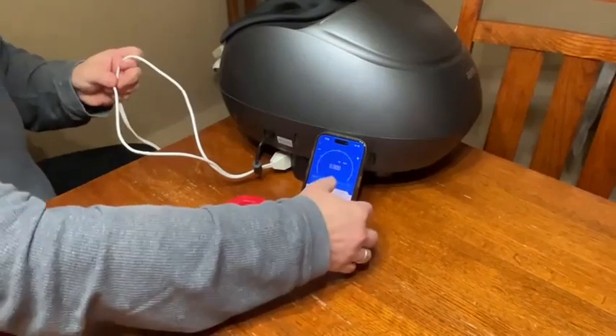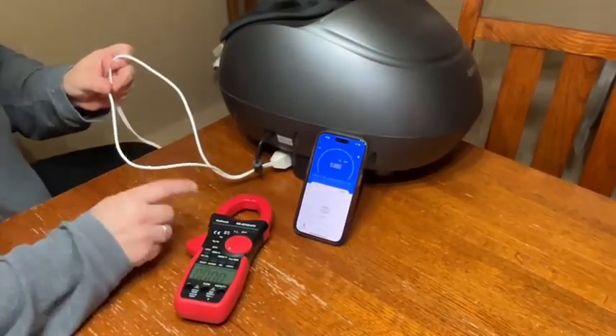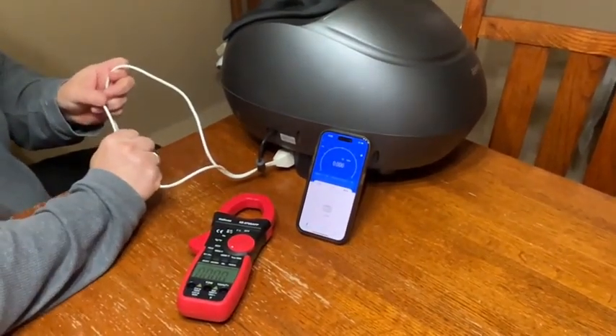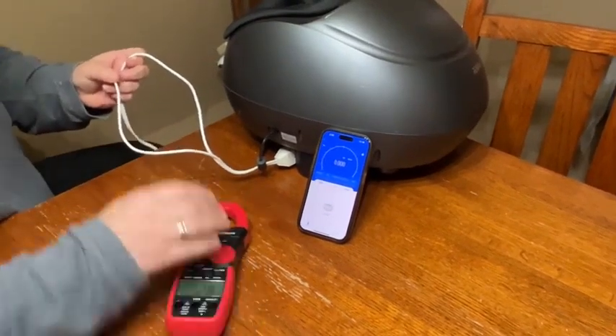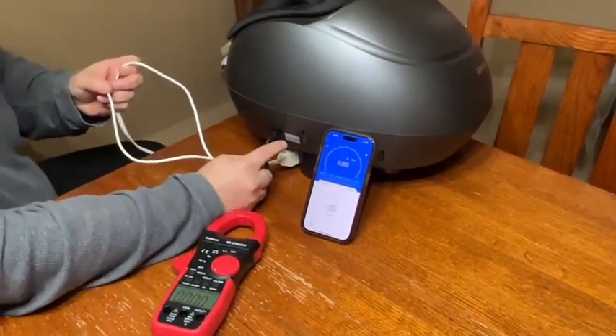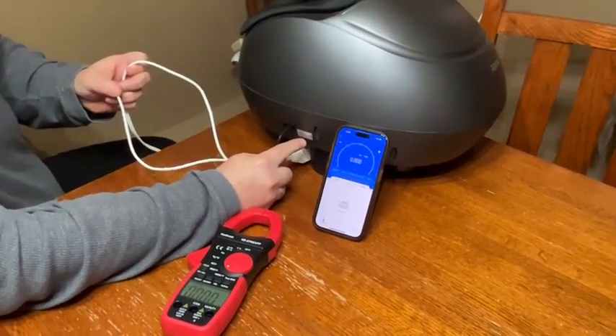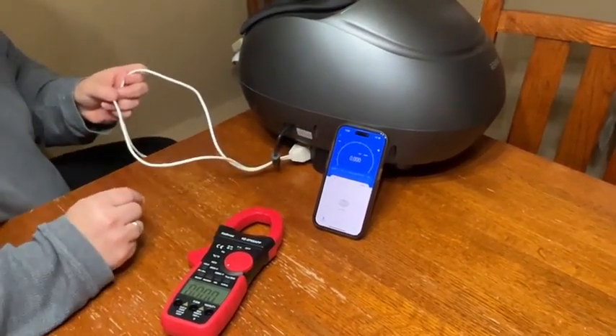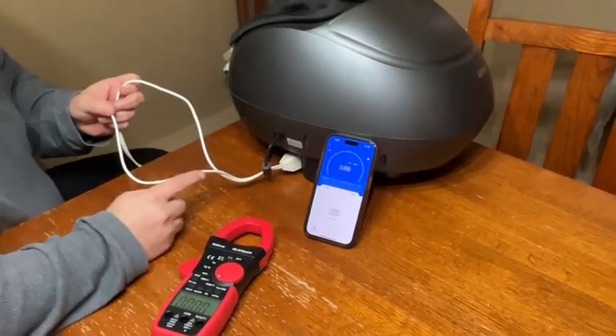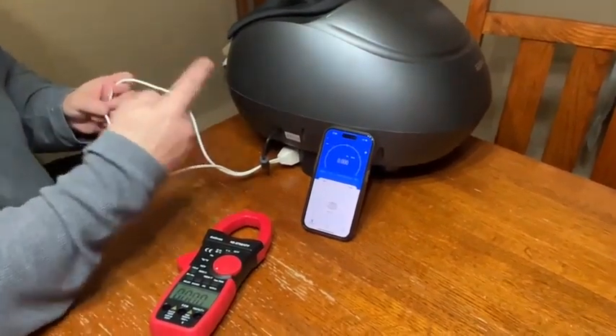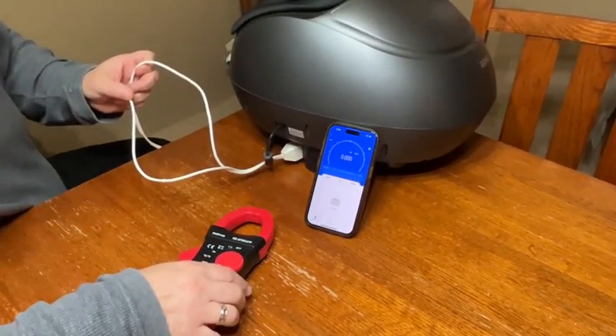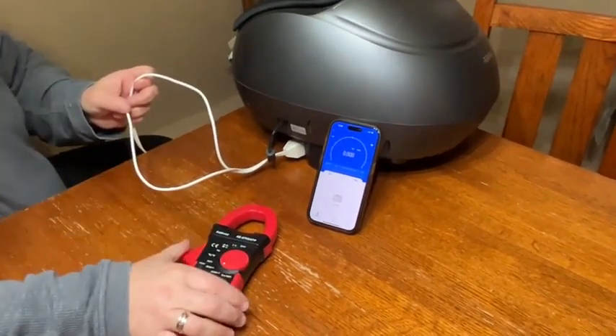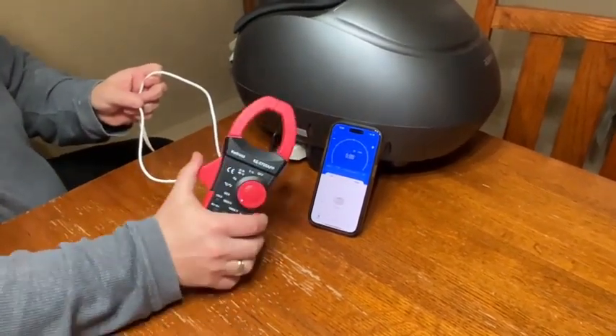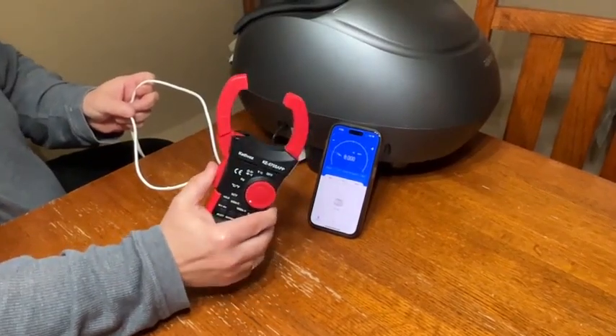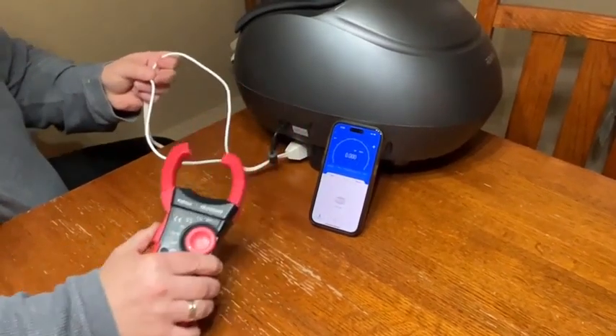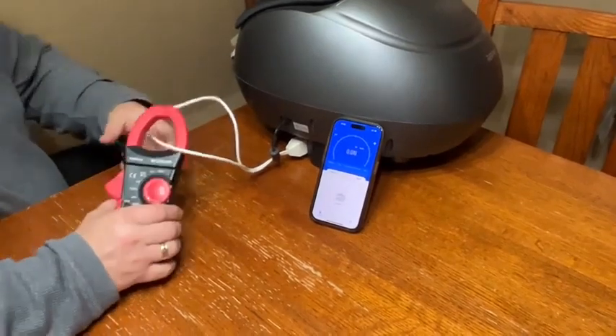So how this clamp works is you need to clamp over a wire that you're trying to measure the current. On this machine, this is a foot massager, a 12 volt or 2.5 amp machine. I chose this as a demonstration because as it's going through its cycles, you'll actually be able to see on the meter the current moving up and down. I'm going to take the clamp and open this up. You can see how wide that clamp opens, so you can get it around a lot of different types of things.